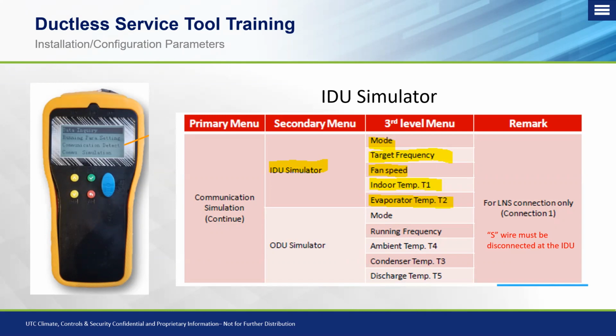Okay, so just to rewind, when we're going to our main menu, this is still in the communication simulation menu. You just need to select either indoor unit simulator or outdoor unit simulator. So the indoor unit simulator is going to be for that L, N, and S connection only. And of course, we know that the S wire must be disconnected at the indoor unit that comes from the outdoor, and we wire in our signal wire that comes with the harness for the LNS connection on the service tool.